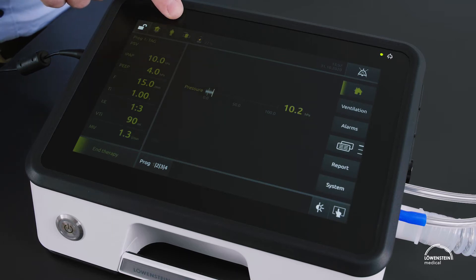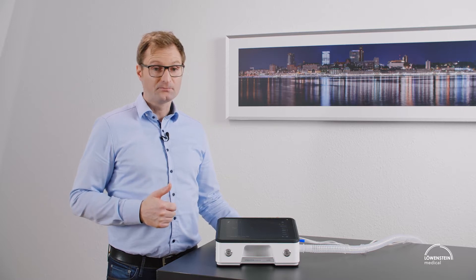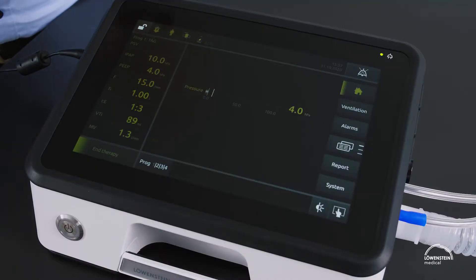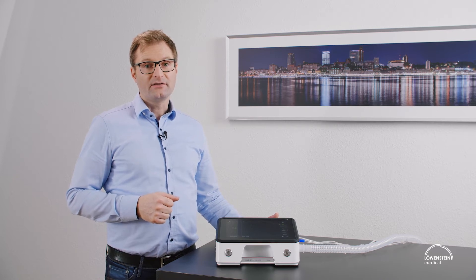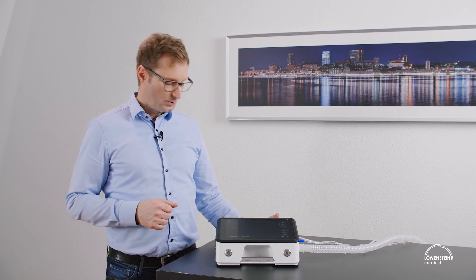Next to it is the patient type. We can set the device to pediatric settings as of 30 milliliters of tidal volume and to adult setting. The circuit type is also displayed. You can use leakage circuits, single circuits with valve, double circuits — all circuits in 15 and 22 millimeter, and the double circuit even in 10 millimeter up to 50 milliliters of tidal volume.